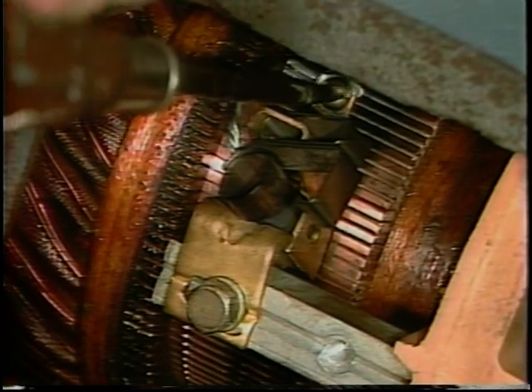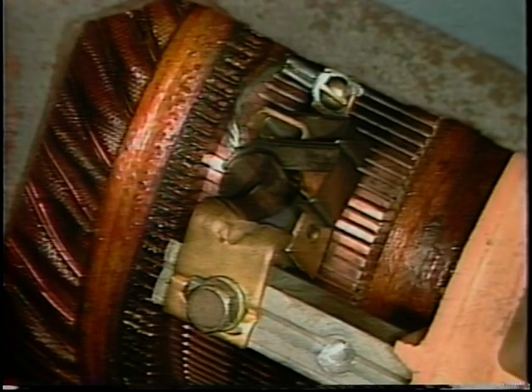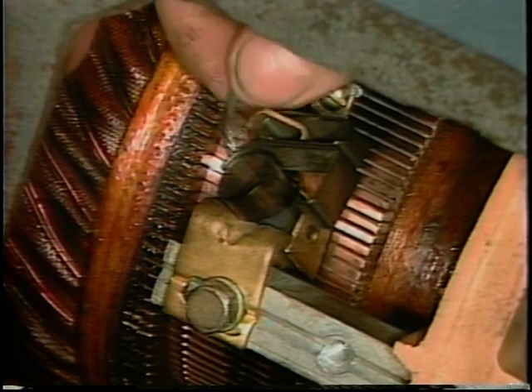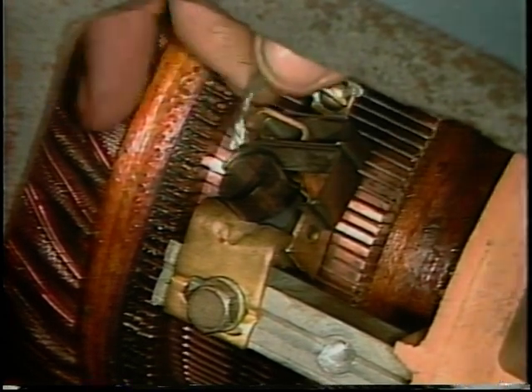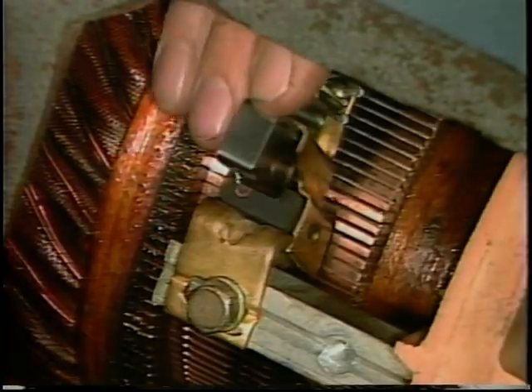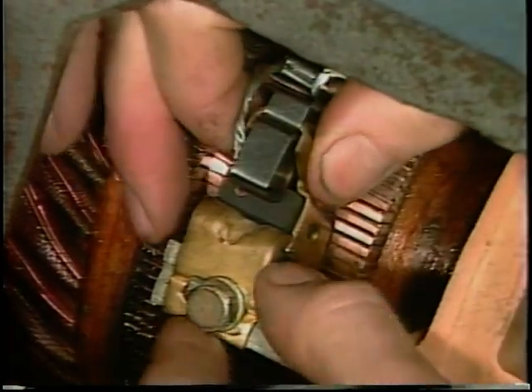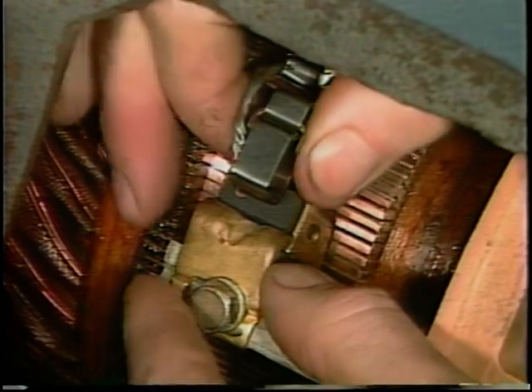Also, be sure the flexible brush leads are not grounding out anywhere and that any insulation on them is in good condition. Check especially carefully the brush holder that any short brush came from to be sure it is not loose, crooked, or out of position.